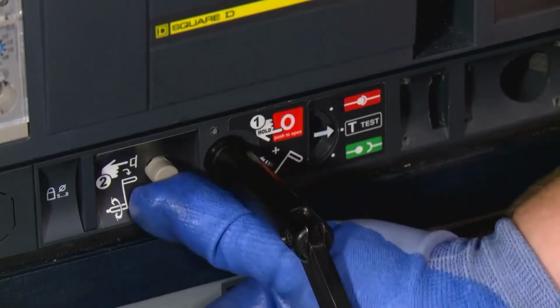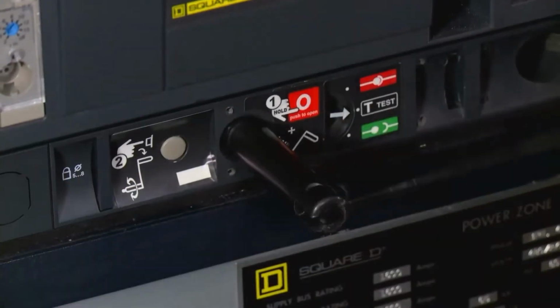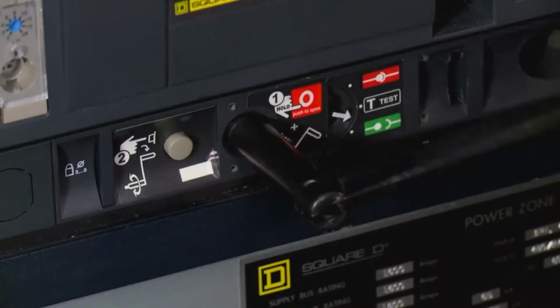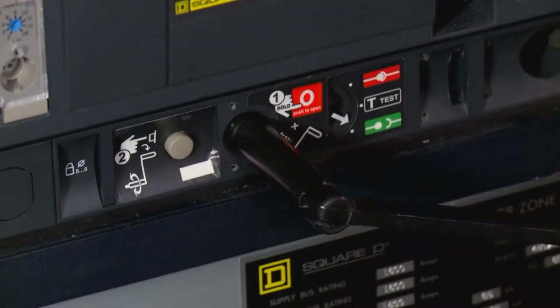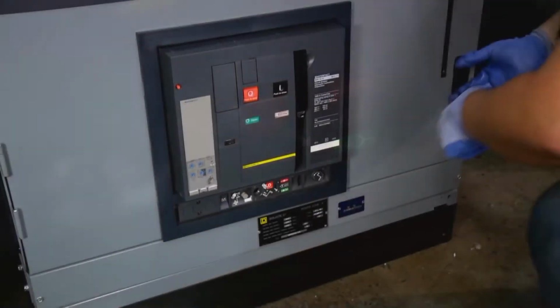Now push the button on the bottom of the cradle. That allows you to keep turning the rack handle counterclockwise. Do so until you reach a disconnected position. The arrow will point at a disconnected line image and you will hear another click. That tells you the breaker is successfully in the disconnected position.